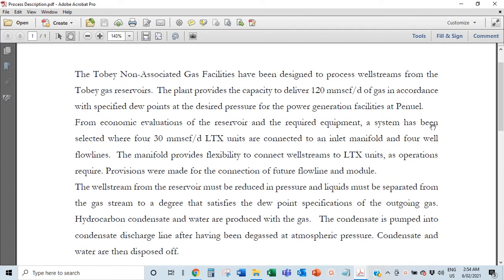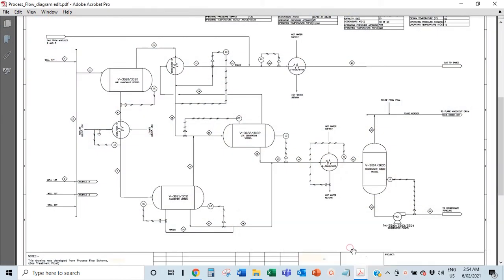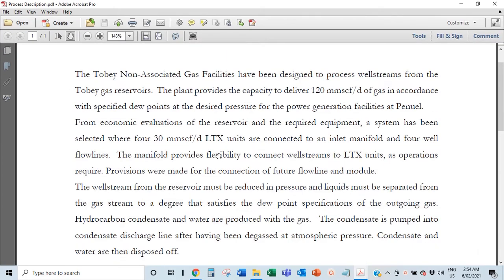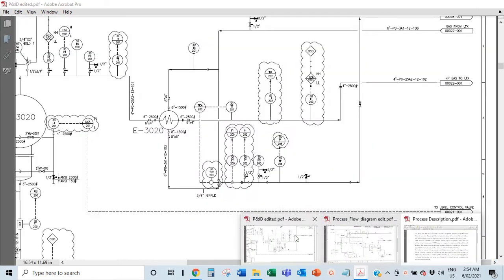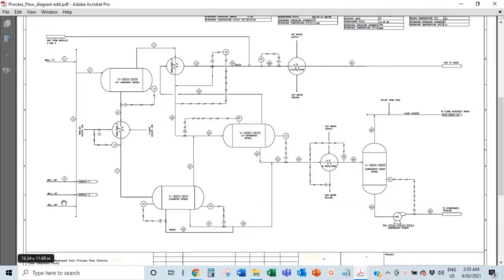Here's a snapshot of the process description. I put the name 'Toby Non-Associated Gas Facilities.' When you hear non-associated gas, it means the gas comes out mostly dry — associated gas means there's some liquid with it. The process description states the facilities have been designed to process well streams from gas reservoirs. The plant provides the capacity to deliver 120 million SCFD in accordance with specified dew points at the desired pressure for the power generation facilities at Penwell.